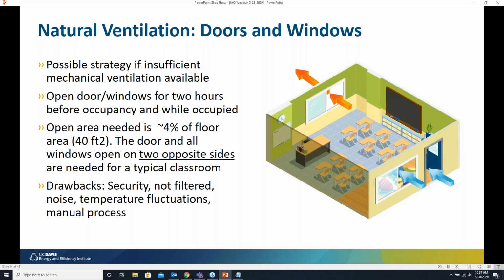Okay, so if for whatever reason you still can't get enough mechanical ventilation into your room, now what do you do? If insufficient mechanical ventilation is available, using your doors and windows is still a fairly decent option if you have windows on opposite sides of your classroom, and when you open the windows and doors, you have at least 4% of the floor area open. For example, a 960 square foot classroom would need 40 square feet of open windows and doors, which is approximately what you would expect to have.